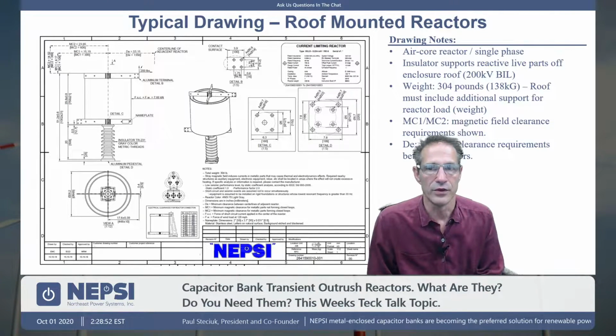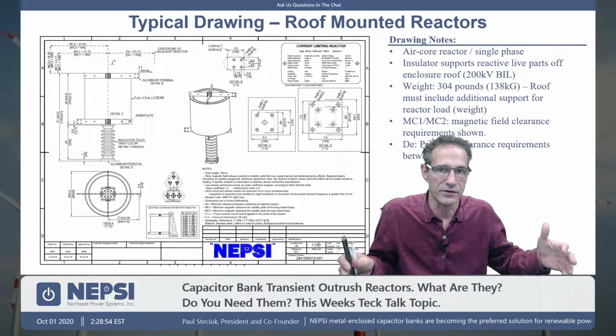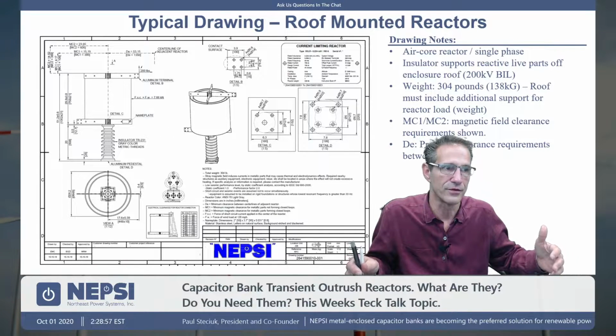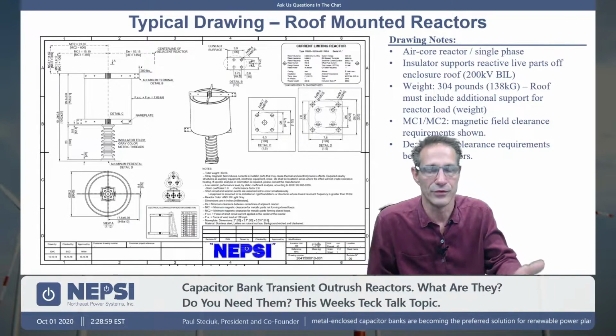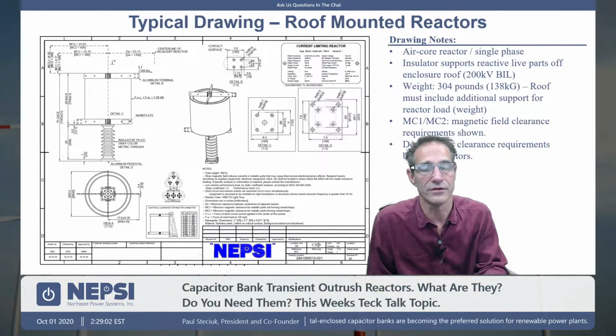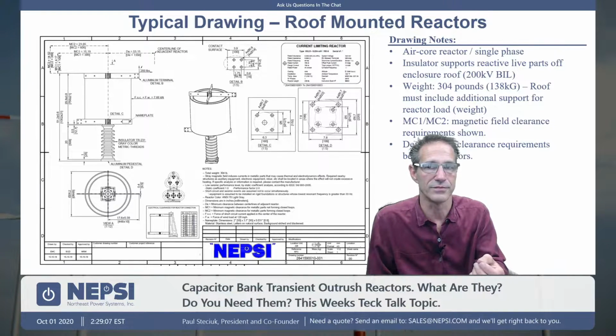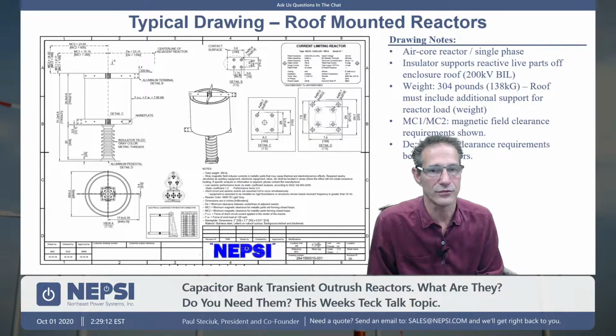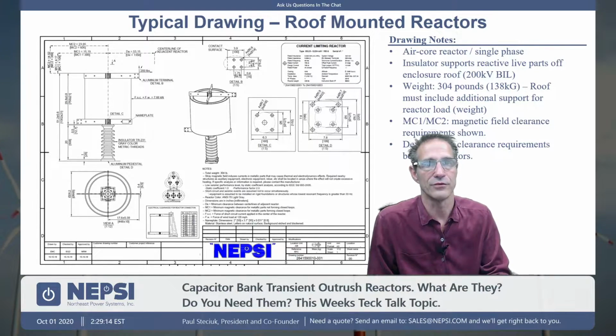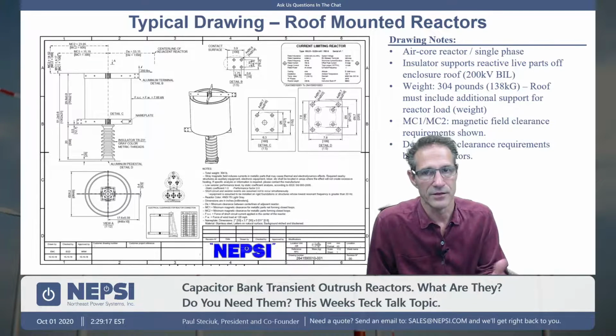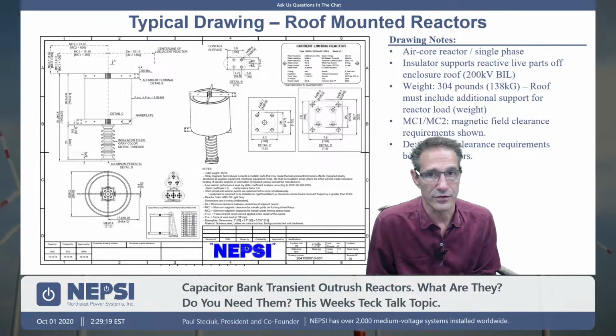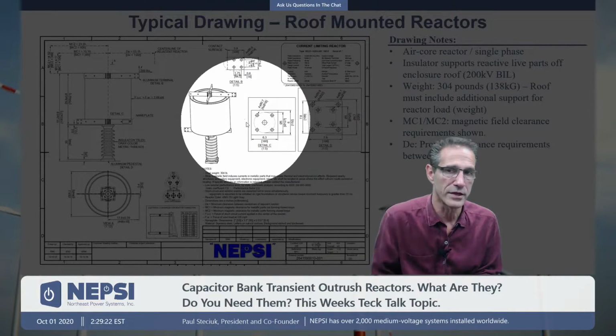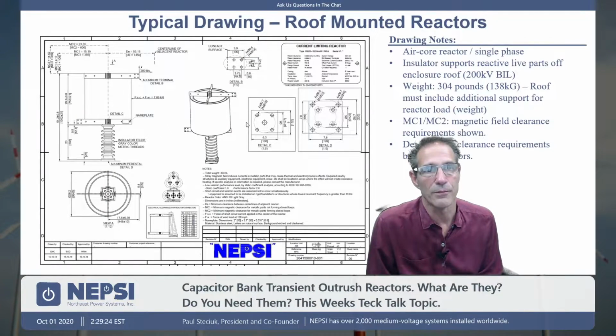So we are dealing with a much bigger space because of the size of the reactor. So in this case, 700 amps, 224 microhenries. That's a lot different than a 40 or 50 microhenry reactor used on a single stage basis. We do not typically have to deal with the heating effect as much when we're dealing with transient inrush reactors as we do with outrush reactors. And then the other thing to take note of is this reactor here, which is the one that you will be looking at on the factory floor, is 304 pounds. So it's a pretty heavy reactor.